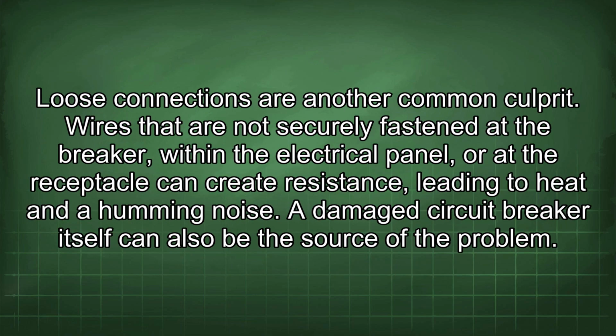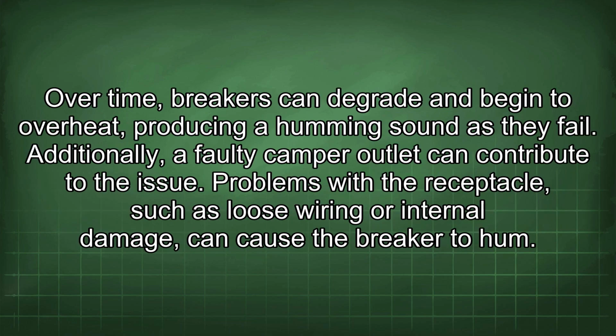Loose connections are another common culprit. Wires that are not securely fastened at the breaker, within the electrical panel, or at the receptacle can create resistance, leading to heat and a humming noise. A damaged circuit breaker itself can also be the source of the problem. Over time, breakers can degrade and begin to overheat, producing a humming sound as they fail. Additionally, a faulty camper outlet can contribute to the issue. Problems with the receptacle, such as loose wiring or internal damage, can cause the breaker to hum.